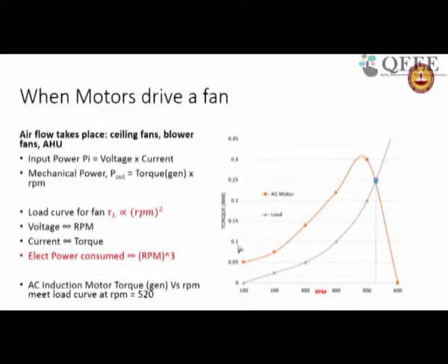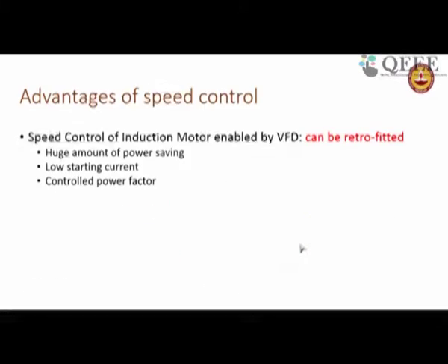So electric power consumed is proportional to the cube of RPM. If I drop the motor speed, power consumption reduces dramatically. If I halve the speed, power consumption goes down by a factor of 8. So when running an air conditioner at a reduced speed by a factor of 2, power consumption drops by a factor of 8. These simple principles can help us achieve major power savings.